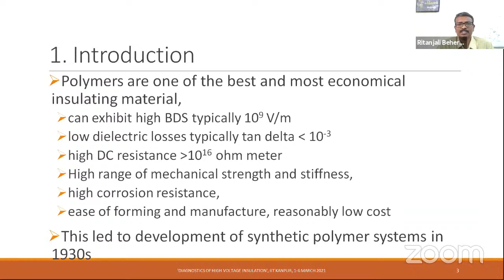Water treeing - I'll spend only one slide on this. Polyethylene was hydrophobic, and so was a choice for power cables in the early 1960s, but it failed within a few years of service due to water treeing. This brought awareness to researchers that under electrical stress, the material goes through complex phenomena, both physical, electrical, and chemical interactions. This led to the introduction of triple extrusion techniques, primarily to prevent moisture ingress and also to improve the dielectric-electrode interface, because water treeing was found to form at this interface.